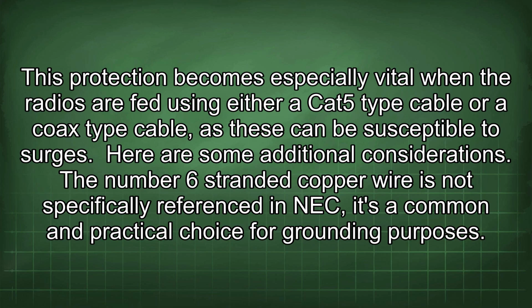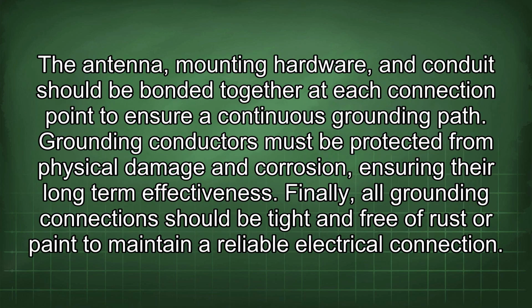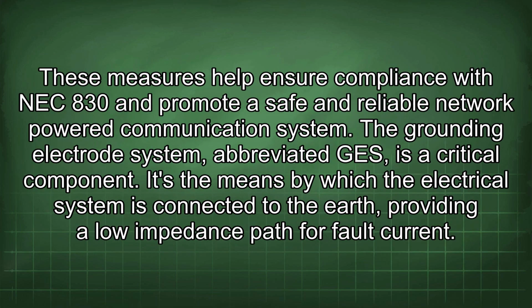Here are some additional considerations. The number 6-stranded copper wire is not specifically referenced in NEC. It's a common and practical choice for grounding purposes. The antenna, mounting hardware, and conduit should be bonded together at each connection point to ensure a continuous grounding path. Grounding conductors must be protected from physical damage and corrosion, ensuring their long-term effectiveness. Finally, all grounding connections should be tight and free of rust or paint to maintain a reliable electrical connection. These measures help ensure compliance with NEC 830 and promote a safe and reliable network-powered communication system.